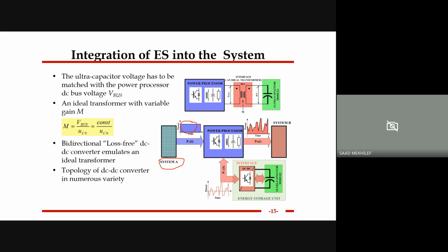Part load condition. So there's a sudden increase or sudden decrease in the load, which maybe the PV system is not enough to cover. So what happens? The diesel generator, and that's the algorithm that we design, has to play an important role: which system has to turn on. If the load increases, the diesel generator will turn on. But what we actually do most of the time is not turn on the diesel generator. We supply the power from the storage system.